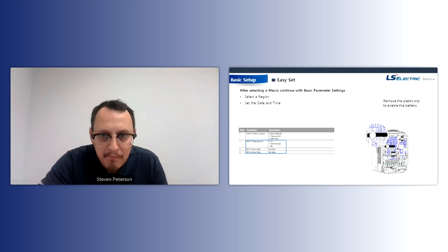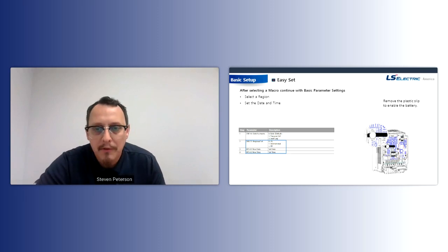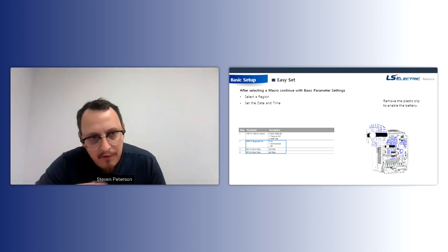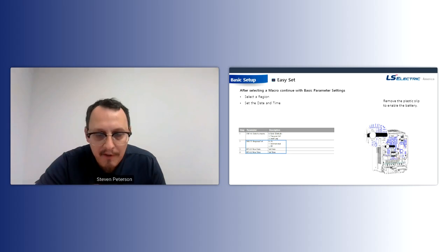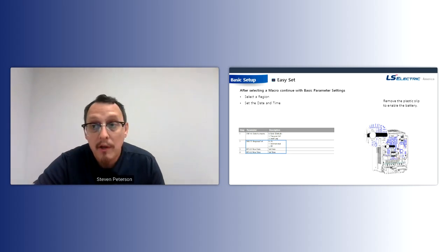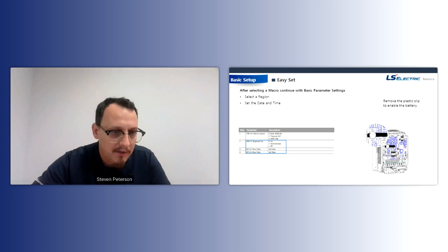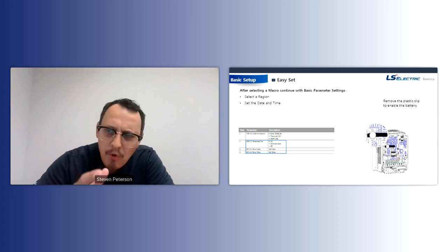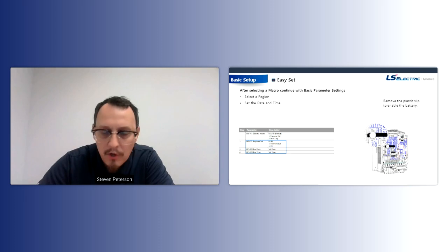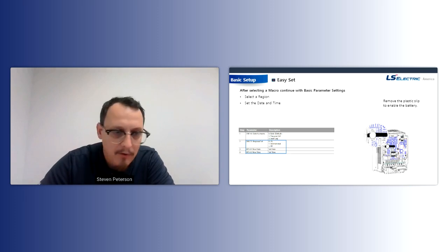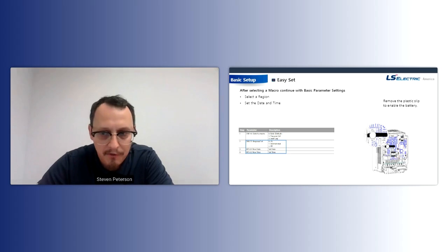Okay, simple enough. Put in your date, put in your time. But there is a trick when you're doing this. There's a little plastic switch or a little plastic slip that's under a battery that's next to the keypad. We'd recommend removing that slip. Just like when you purchase a toy at the store and there's a battery pre-installed, you need to remove that slip to make the battery make contact. Otherwise, you're going to lose that date and time after you cycle power to the drive. And this is a standard CR2032 coin battery, so it's like the size of a quarter. So we'd recommend enabling that battery after you set up the time when you're starting this up.